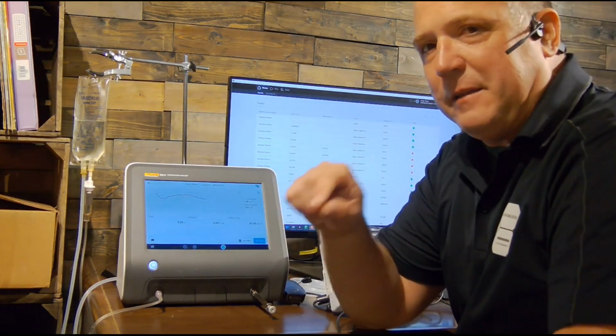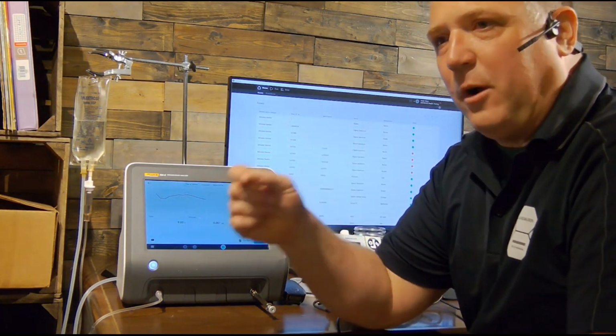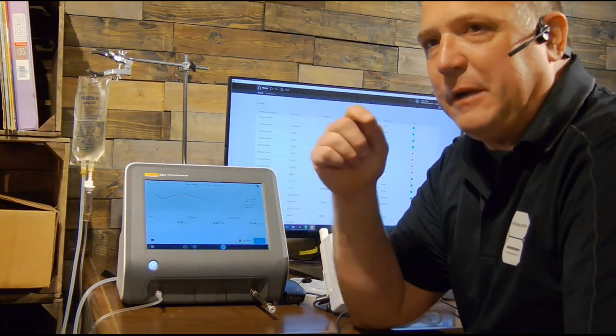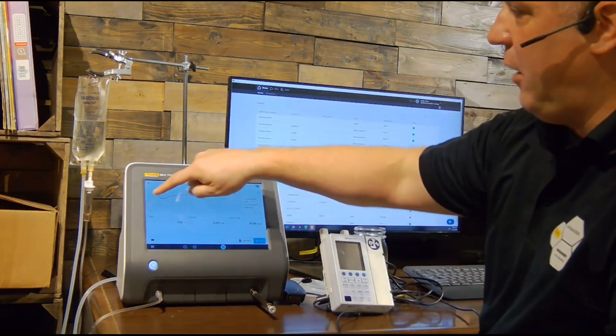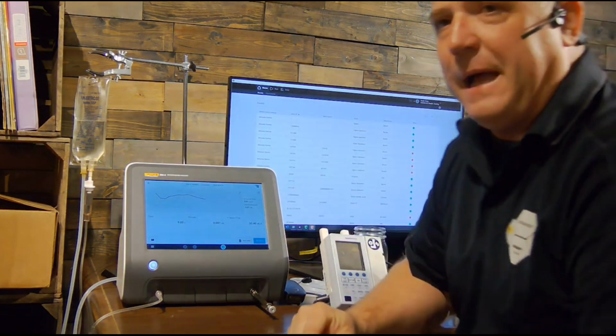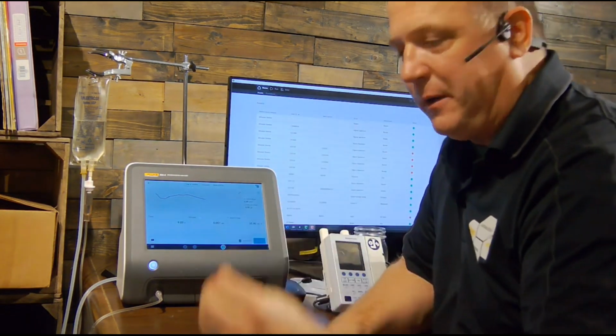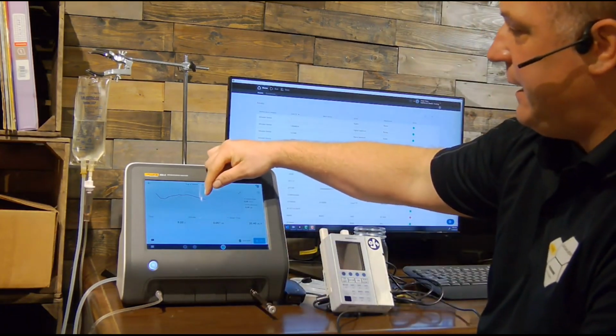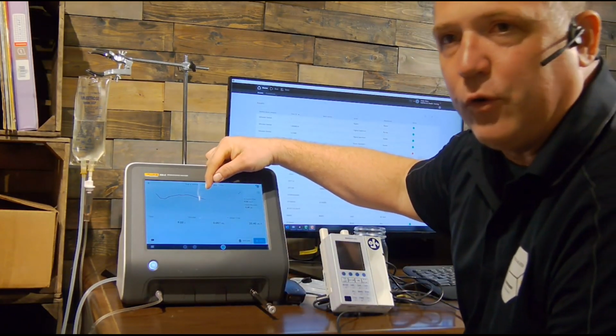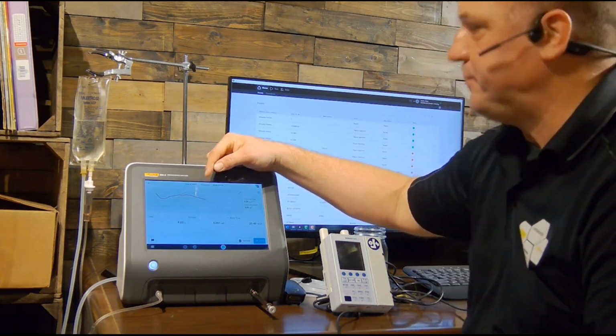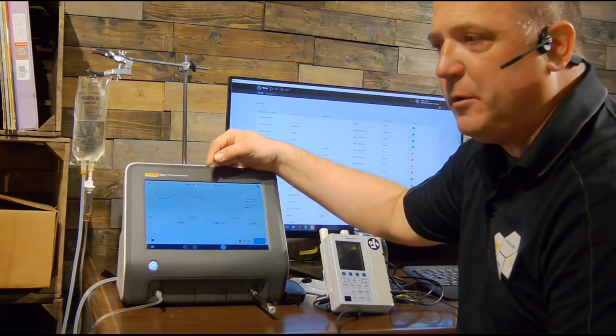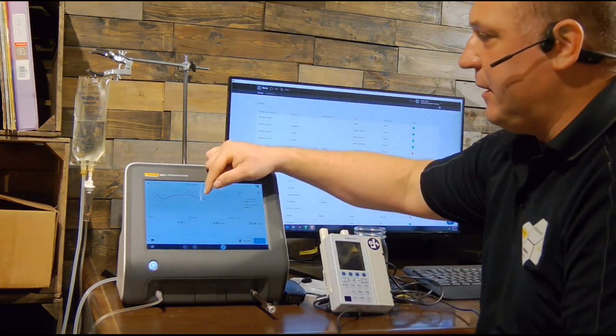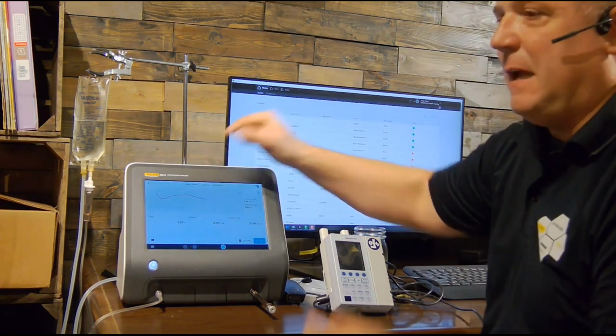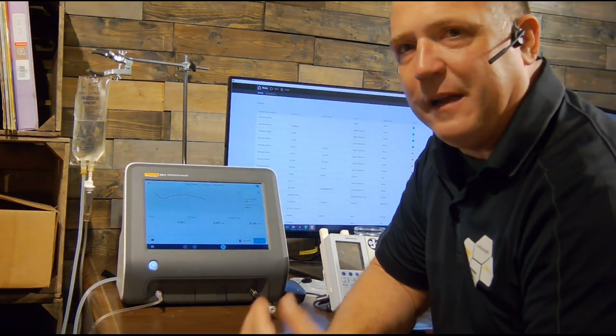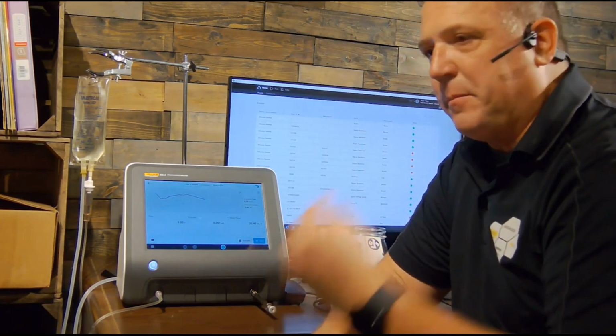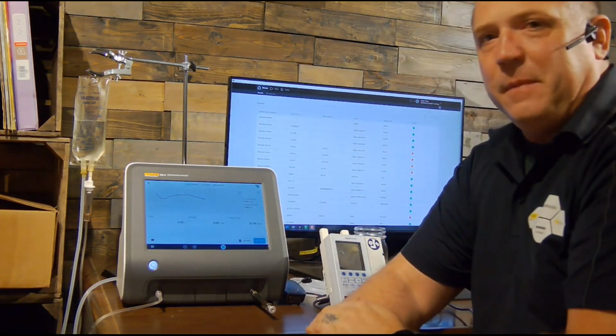Now, what I want to tell you about that is the IDA-6 is so smart that it knows it takes exactly 3 microliters to start a test. So it'll measure the average flow, then go back in time 3 microliters and make that the start point. And at the end of the test, it knows once it sees more than a 50% drop in flow that the test is probably ended. So if it doesn't see the volume go above that 50% mark again, it's going to mark that as the end of the test. And because of this, this feeds into the resolution of the IDA-6 of being better than 1% for most of our tests. And that's just amazing technology.